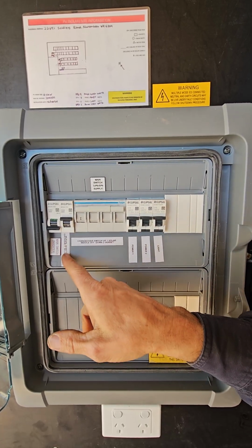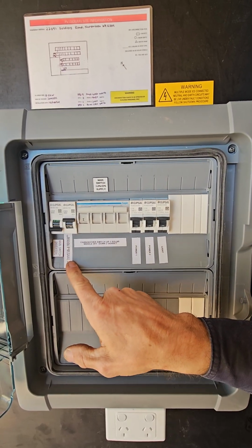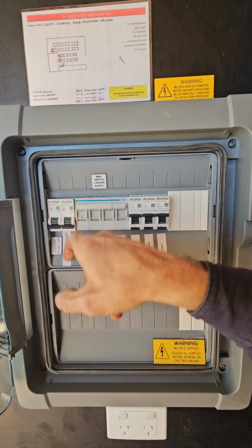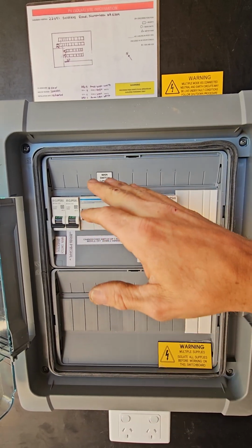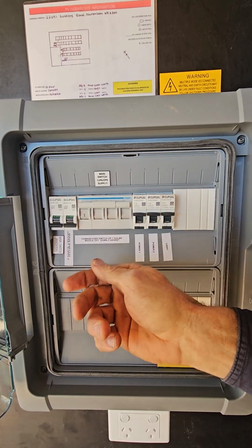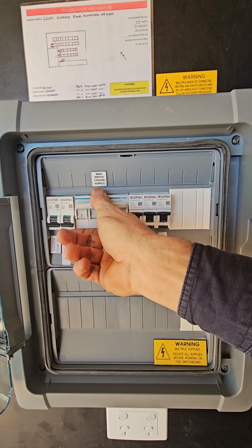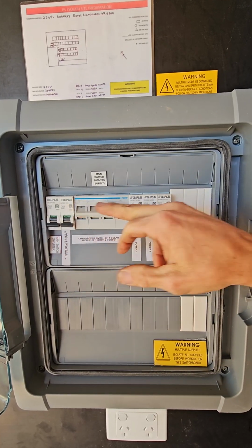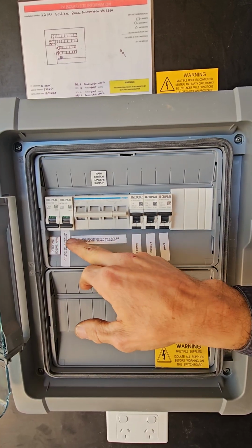But because the generator is not running at the moment, obviously there's no power. So that's your next point of isolation, the main switch generator. So turn the main switch generator off. Then the next one is turn off the main switch UPS EPS supply, which is your main switch for the installation here. So off position is in the middle. There's a description of how this changeover switch works.